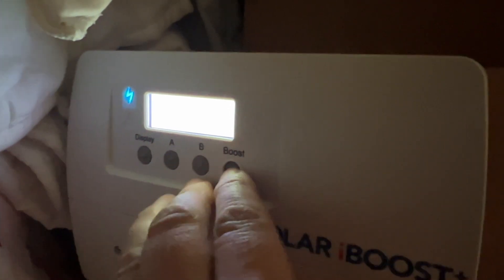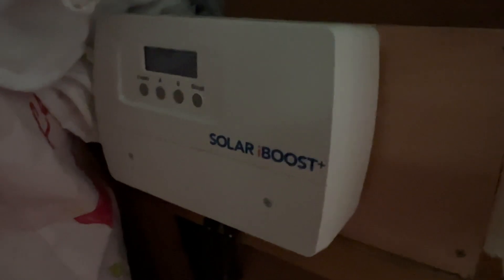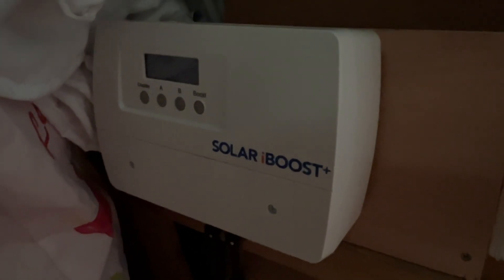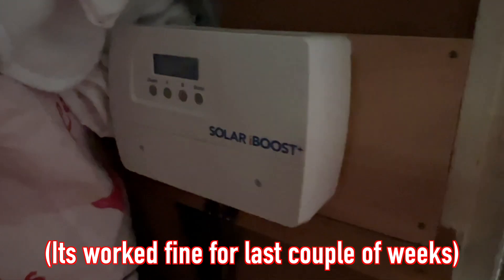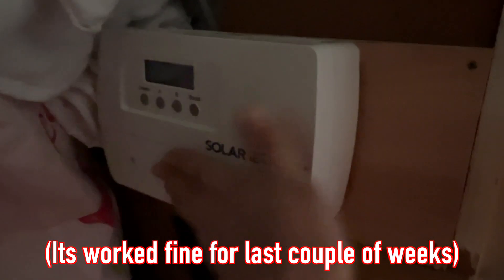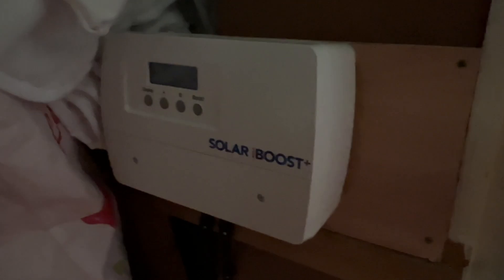I've turned off the charging - I'm going to kill the power to this to stop it. The solar iBoost is pulling straight from the battery even though there's no overage, no spare to be exported to the grid - it's actually pulling two kilowatts consistently from the battery. So I've now killed the power to it to stop it doing that. The solar is only producing 500 watts now, so that energy can go back into the battery.